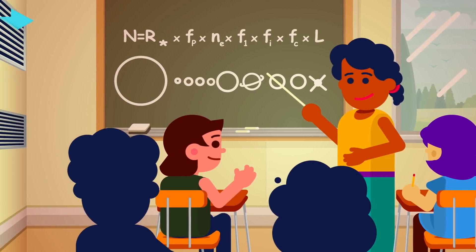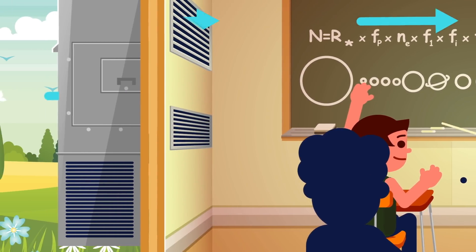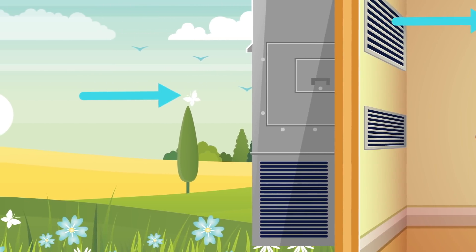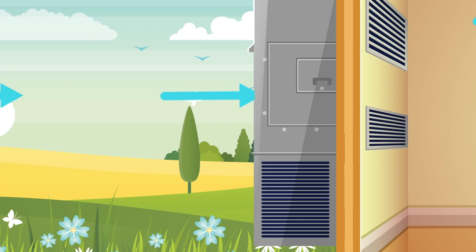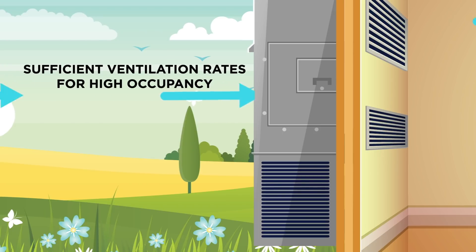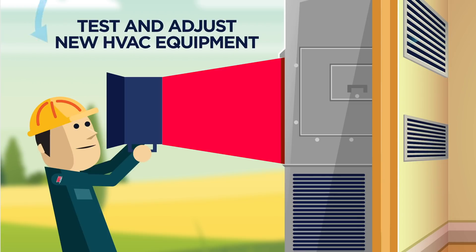We recommend that school districts take the following actions to improve classroom ventilation and indoor air quality. When purchasing new HVAC equipment, select equipment capable of providing sufficient ventilation rates for high occupancy areas like classrooms. When installing new HVAC equipment, test and adjust the system to provide the required ventilation rate. Periodically test existing HVAC equipment to ensure the required ventilation is provided. With minor adjustments, many existing systems will be able to meet ventilation requirements.